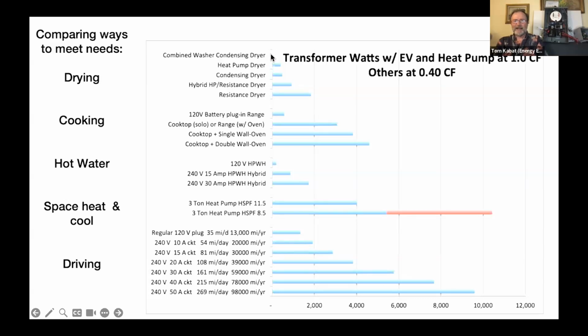And the one I like doesn't add any more to the panel load. It's the combined washer, condensing, or heat pump dryer in one machine. So it's on the washer plug. So that's what frees it up. And here's the regular electric resistance dryer that you're more familiar with. In between are hybrid ones that are part resistance, part heat pump, or condensing or heat pump. Going to cooking, here's that 120 volt plug-in battery range way down there, hardly sipping, just sipping power, versus going to a full cooktop and a double wall oven, which logs in on the panel calculations for your code compliance at over 4,000 watts. So it's taking up more panel space to do that.